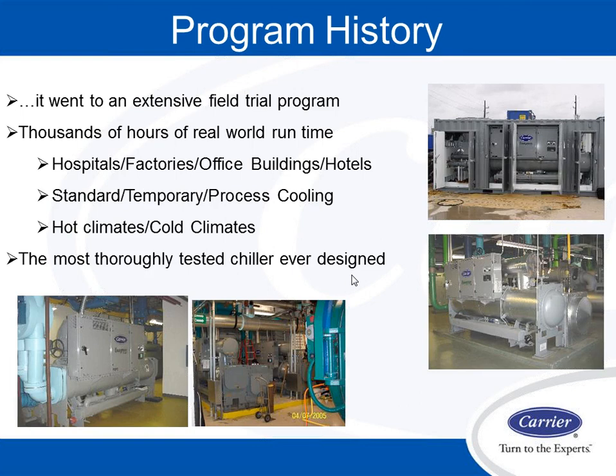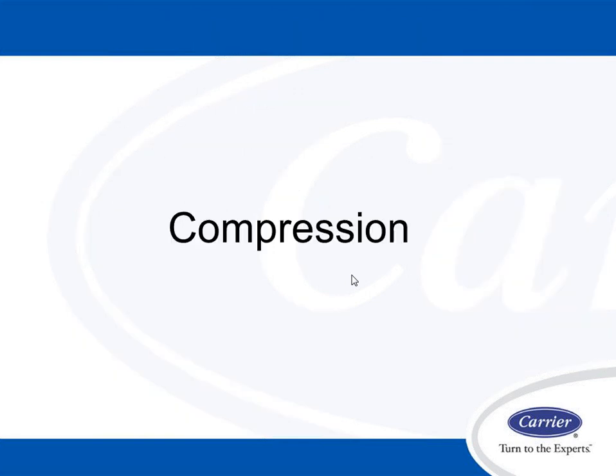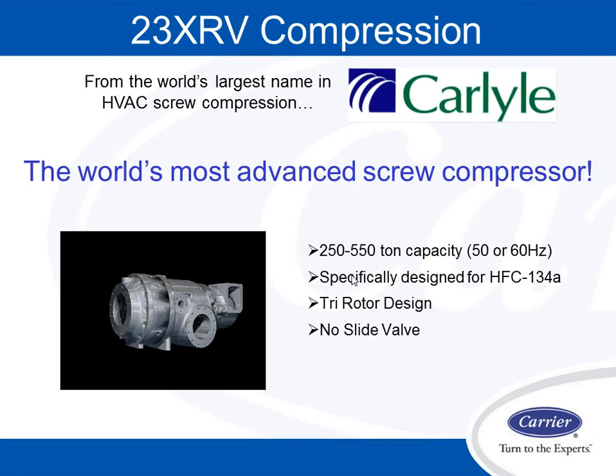We'll briefly discuss that later on here. So what they did is it went through the most extensive field trial program they've ever had. So they have thousands of hours of operating in factories, hospitals, office buildings, temporary cooling, hot, cold climates. Everything you could think of, they tested in these conditions. So this is where this machine starts getting interesting, which is basically the compression part of it. The machine, again, Carrier makes the compressor in Charlotte, North Carolina. They have two sizes, 250 to 400 and then 400 to 550, specifically designed around 134A, a tri-rotor design.